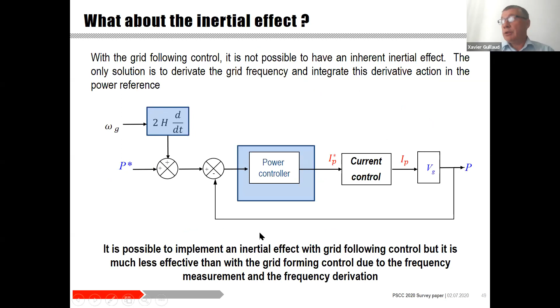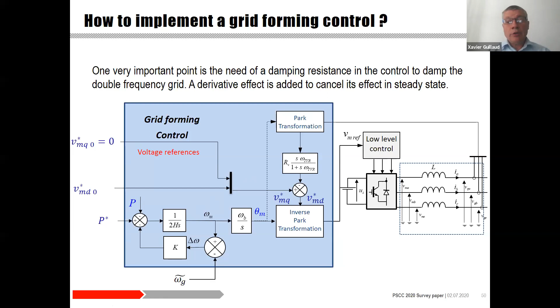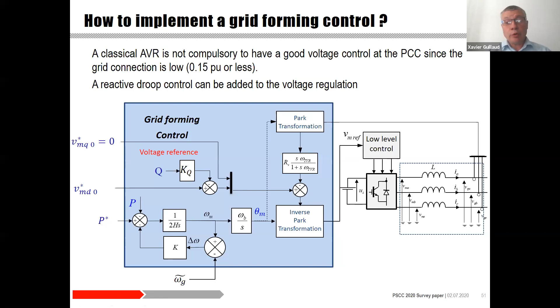The aim of the control is to generate a set of references for the modulated voltage V ABC. The grid forming control generates the angle theta. The magnitude of the voltage is chosen with a DQ command and applied on an inverse Park transformation to generate the voltage ABC reference. Due to the very small R over X ratio in transmission systems, the poles of the grids are not very well damped. This is the reason why we have to add a damping resistance during the transients. This is extremely important in transmission applications. Since the connection impedance to the grid is very small, around 0.15 per unit or less, closed loop control for the voltage is not compulsory to have a good voltage control of the VSC. A reactive control can be added if needed.